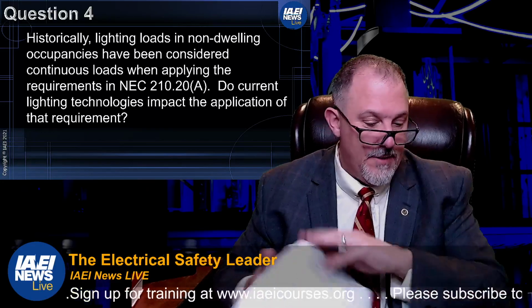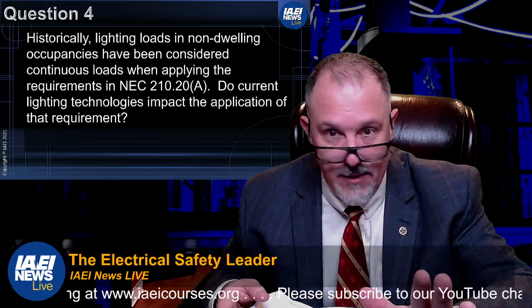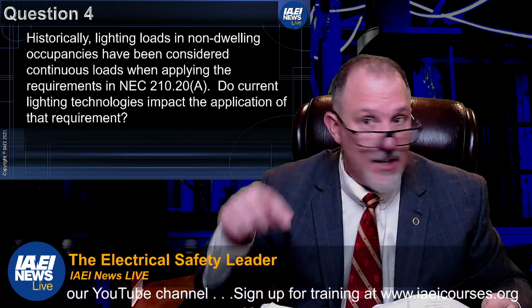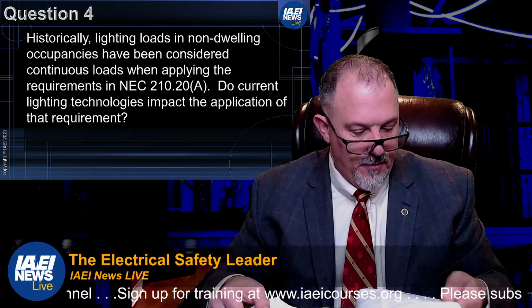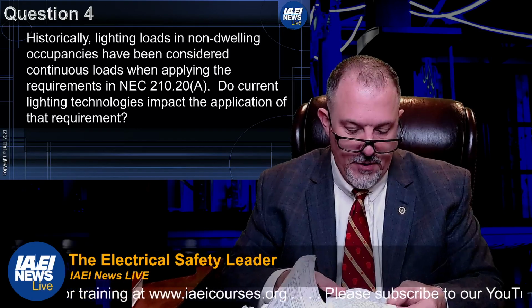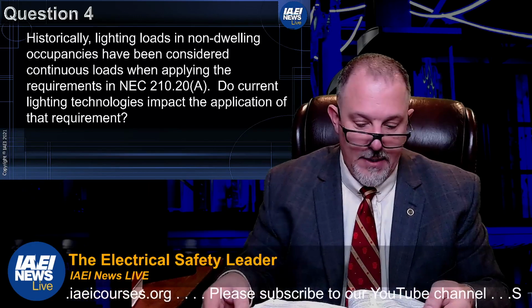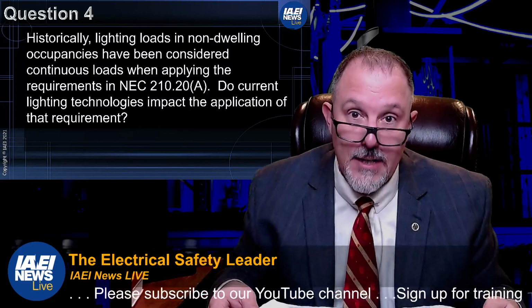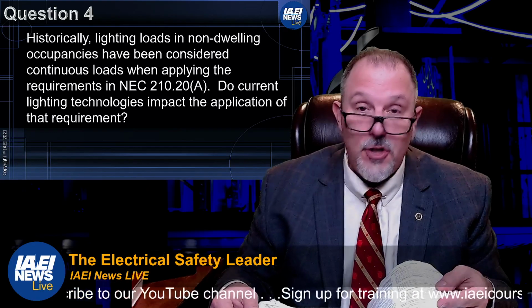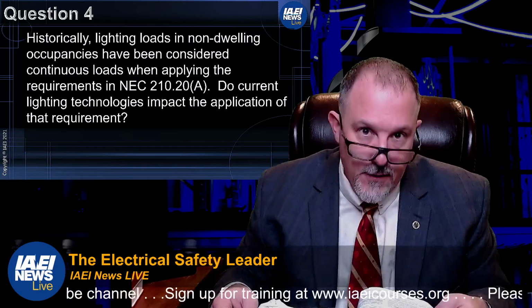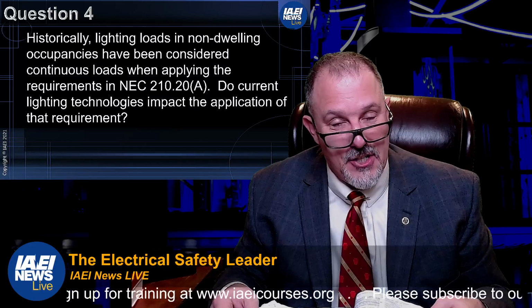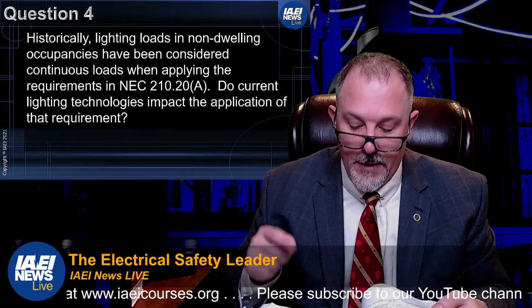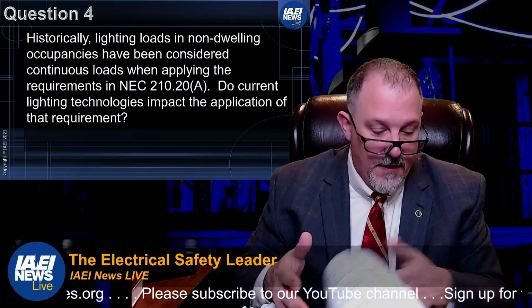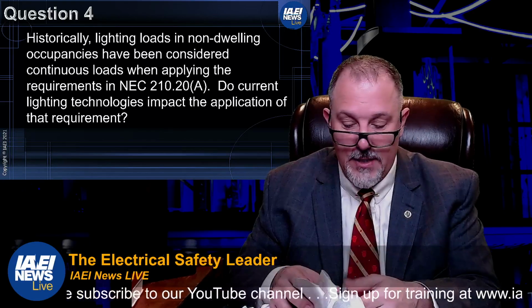what is a continuous load? I know I'm bouncing around a little bit, but hopefully you can go back and think about what I'm saying in all of these sections. Think about 220.12, where the 125% is worked into the table. Think about 215.3 that says you need to do two different calculations. So make sure I got the right numbers. 215.2 is the minimum ampacity. 215.3 is overcurrent protection, right? 215.2 is the one I'm thinking about that says you have to do a calculation first based upon the 125%, second based upon conditions of use, right? And if the VA per square foot already includes the 125%, do I need to back that out? Think about the sections in 210.20 for an example.